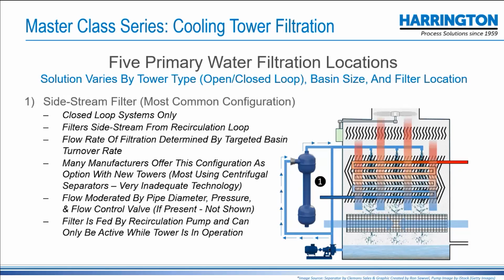Well, your pump is going to be recirculating at far more than that. So in this kind of scenario, a percentage of the pumped water, which is a percentage of the reservoir volume, is being separated. So you're treating a percentage of a percentage. You're not treating all of the water, so you're still getting solids and debris, sludge, and other contaminants back through those spray nozzles and over the dispersal element. So it's really intended to, over time, reduce the solids in the basin, but not really preserve the equipment itself. So even if you had the world's best filter in that location, you still would only get partial results. So many manufacturers who sell cooling towers, as I said today, will use this.